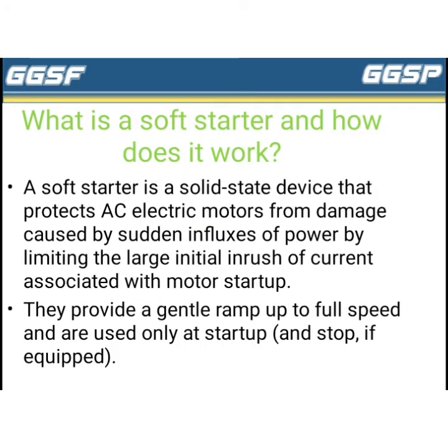What is a soft starter and how does it work? A soft starter is a solid state device that protects an AC electric motor from damage caused by a sudden influx of power by limiting the large initial inrush of current associated with motor startup. They provide a gentle ramp up to full speed and are used only at startup, and at stop if equipped.